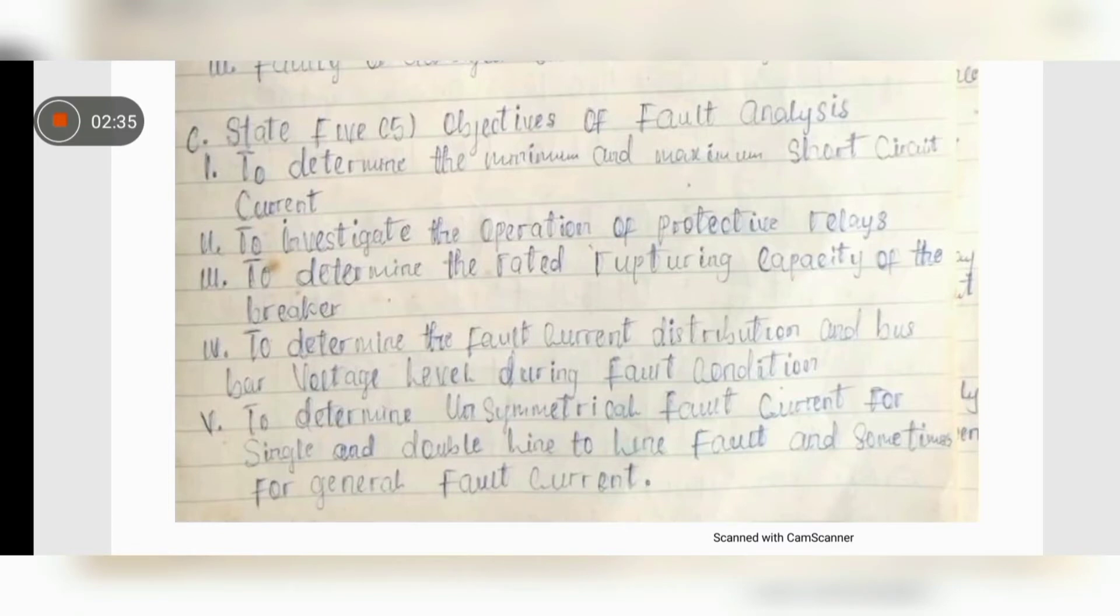We have to state five objectives of fault analysis. To determine the minimum and maximum short circuit current. To investigate the operation of protective relays. To determine the rated rupturing capacity of the breaker. To determine the fault current distribution and bus bar voltage level during fault condition. To determine unsymmetrical fault currents for single and double line to line fault and sometimes for general fault current.